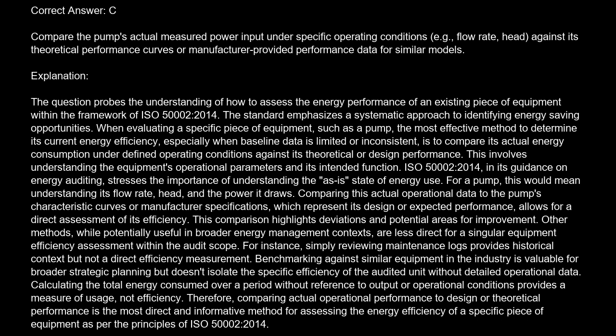ISO 50002, 2014, in its guidance on energy auditing, stresses the importance of understanding the as-is state of energy use. For a pump, this means understanding its flow rate, head, and the power it draws. Comparing this actual operational data to the pump's characteristic curves or manufacturer specifications, which represent its design or expected performance, allows for a direct assessment of its efficiency. This comparison highlights deviations and potential areas for improvement.